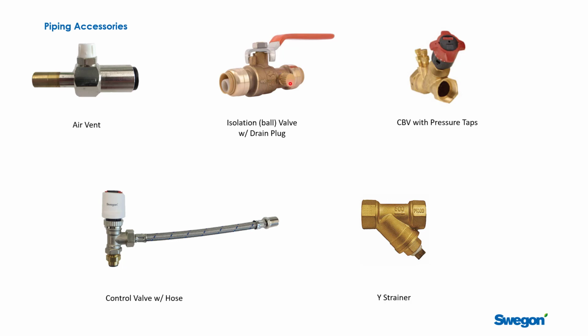You can potentially order the beams with a drain plug in them, but it's often done in the piping and the hoses, so you can drain whatever water's between the two valves and whatever's in the coil. And when you break the hose connection, you'll be able to catch that water in a bucket if you ever needed to drain down a coil for some service reason.